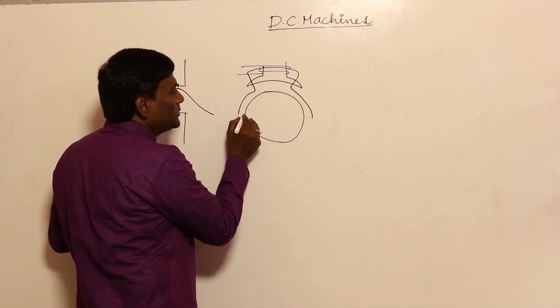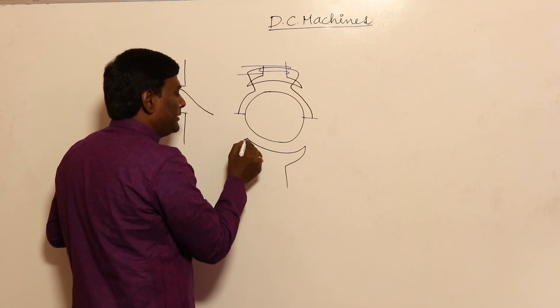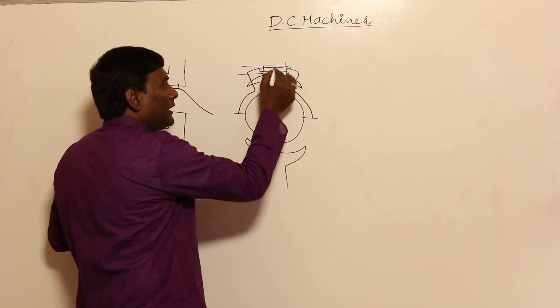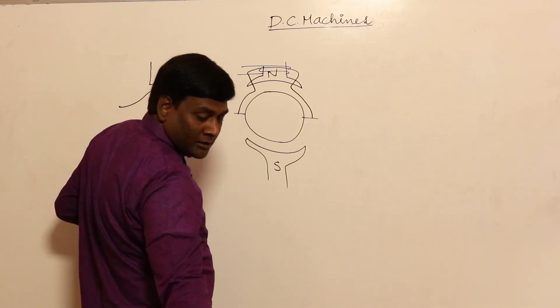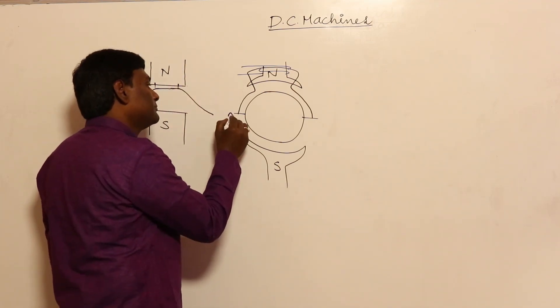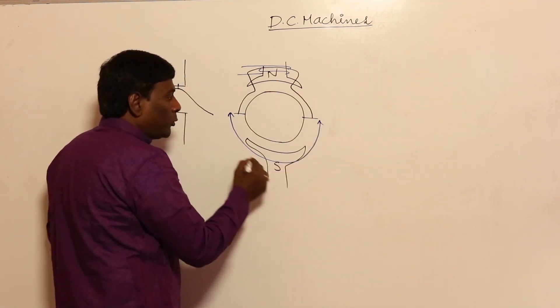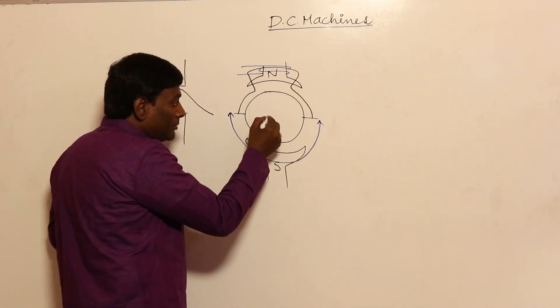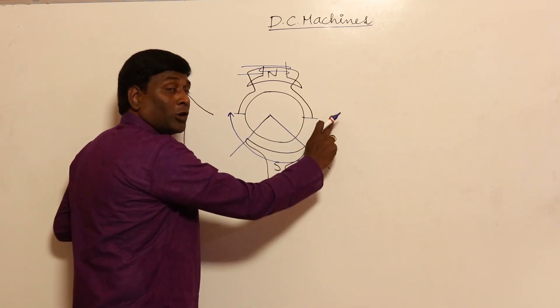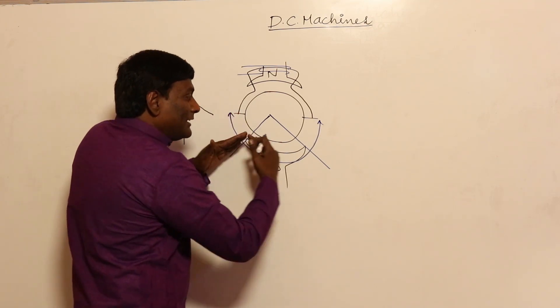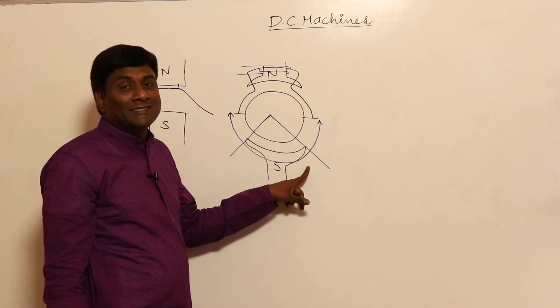Anyway, pole shoe area should be increased. Out of total pole pitch — for example, from here to here is the pole pitch, with N pole here and S pole here — pole pitch is the total area from one pole to the next. Out of the total pole pitch area, if I can increase the pole shoe coverage, automatically from here to here the flux density waveform can be flat-top.